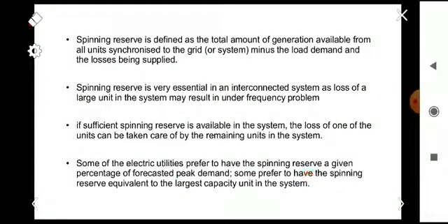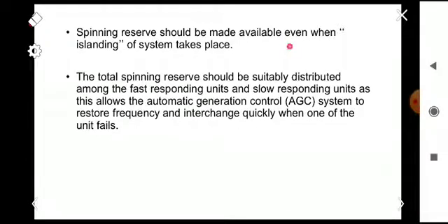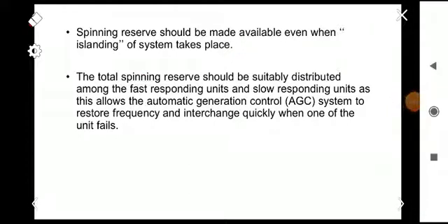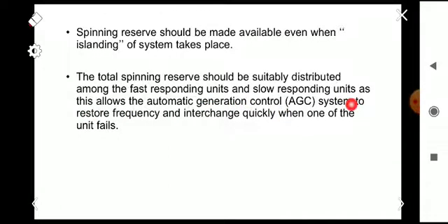Some electric utilities prefer to have spinning reserve as a given percentage of forecast peak demand; others prefer spinning reserve equivalent to the largest capacity unit in the system. Spinning reserve should be available even when islanding of the system takes place. The total spinning reserve should be suitably distributed among fast-responding and slow-responding units, allowing the automatic generation control system to restore frequency and interchange quickly when a unit fails.